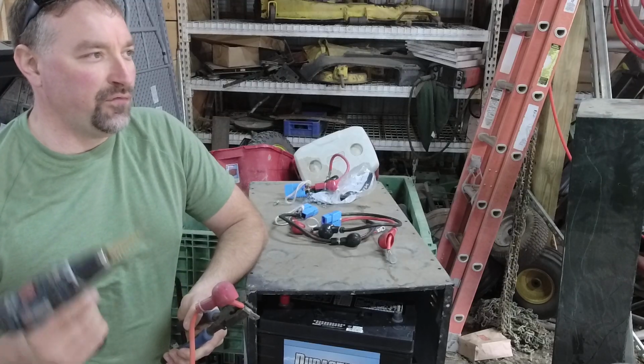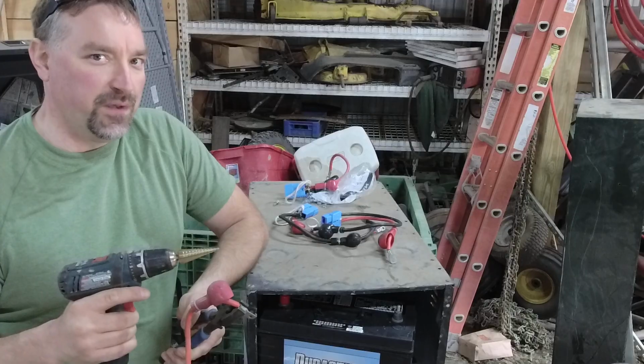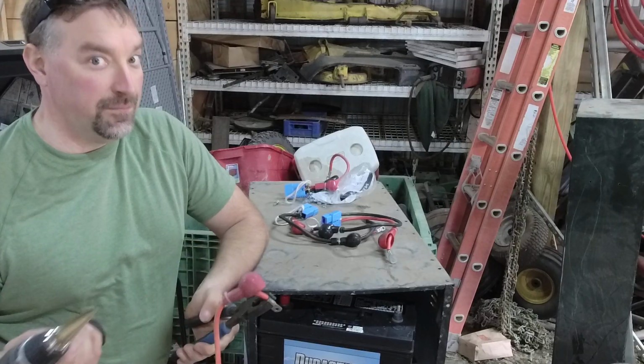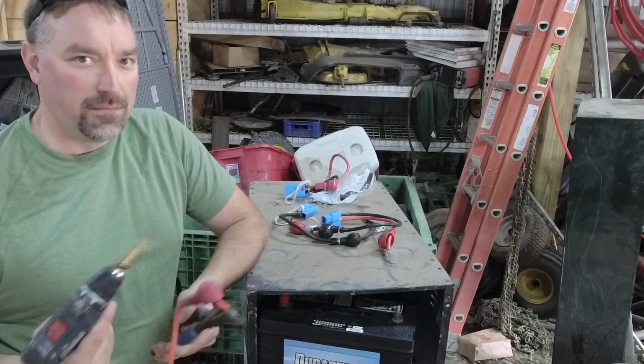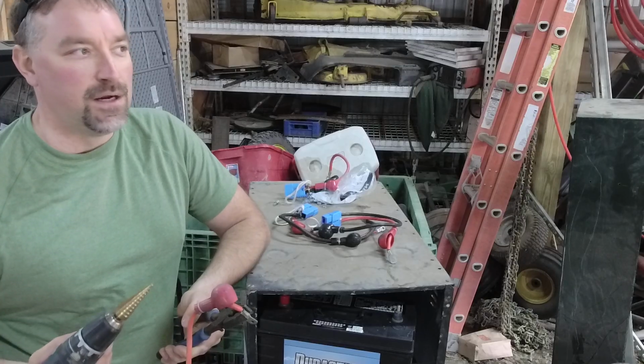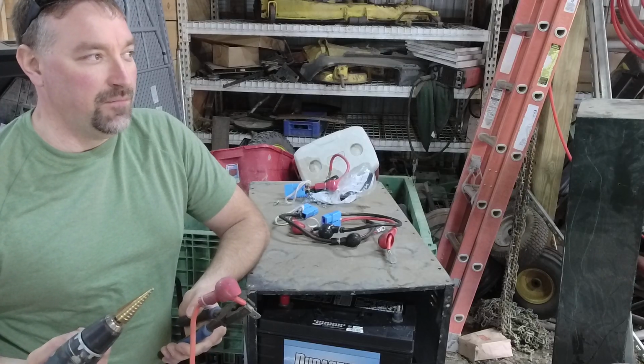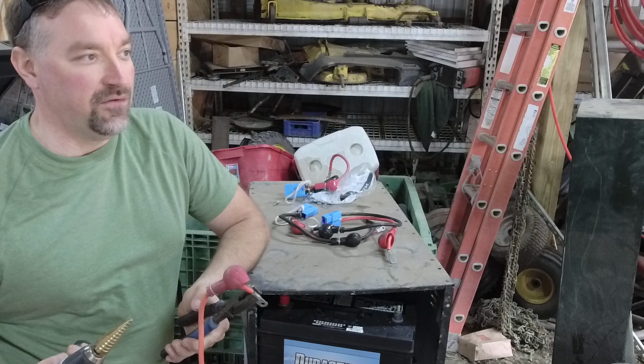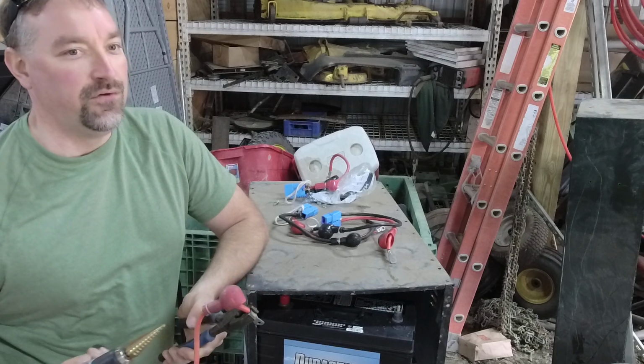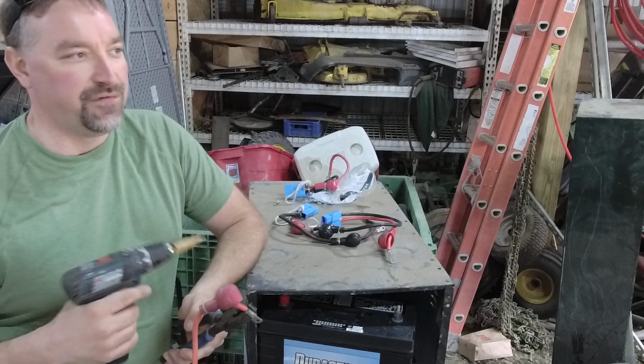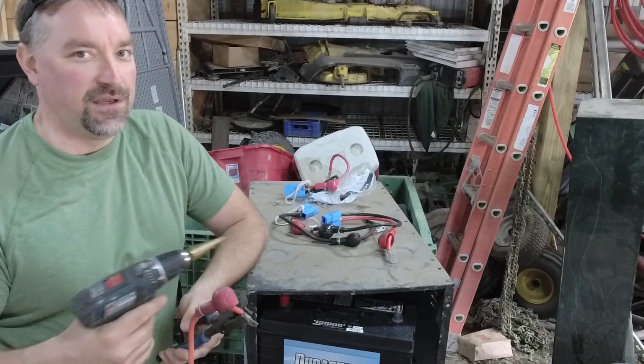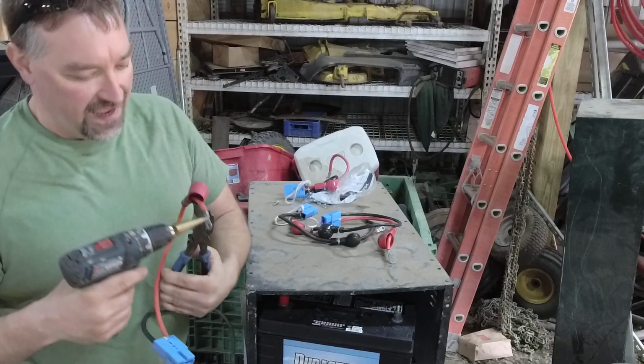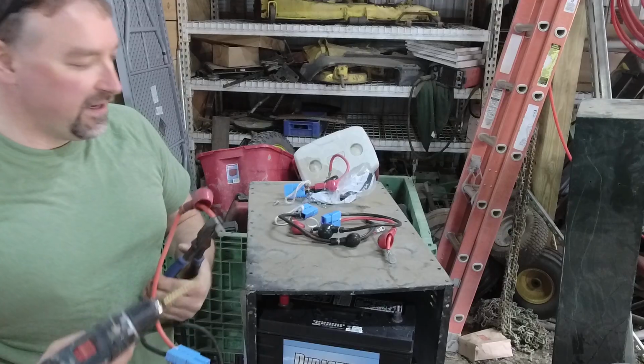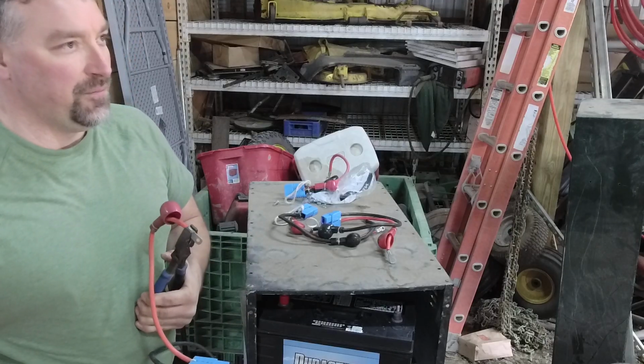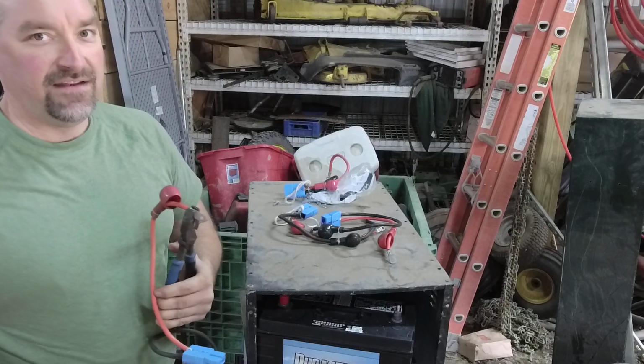But those fire alarms are actually plugged into the UPS. The idea being, if we lose power at the site, I still want to be able to monitor for fire - because maybe the reason we lost power in a building is because a mouse or something chewed on a wire, and I don't want the fire alarm to not notify me when something happens. So that's all backed up by UPS - hence we've got to get that UPS in a better state.